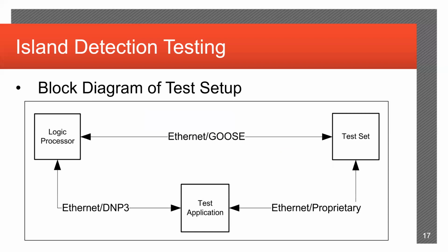From a block diagram standpoint, it looked like this. The test application would communicate to the test set over here on the right, which would publish Goose messages representing all of the various combinations sequentially, of course, one at a time, to the logic processor. The logic processor would then make a determination of whether any one generator was in parallel with another, etc. And then the test application would poll the logic processor via DNP3 to get the answers, and then compare that to the answer key.